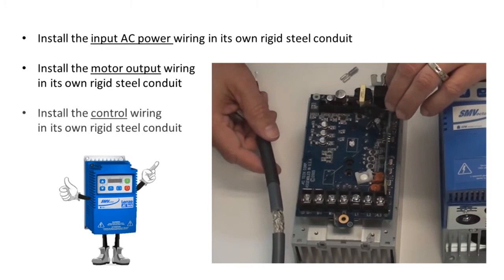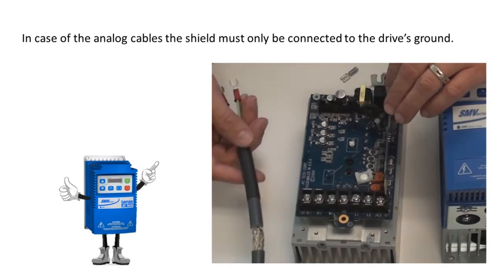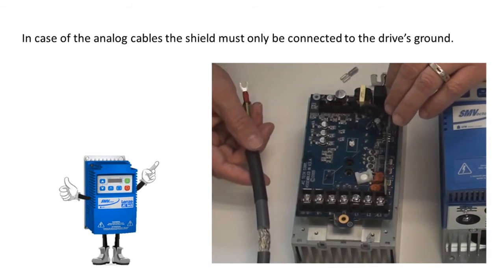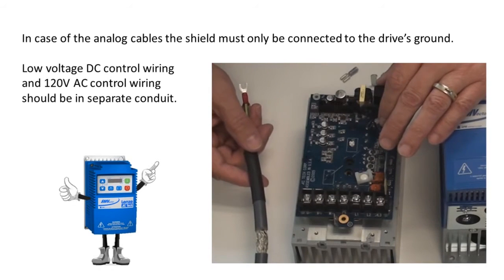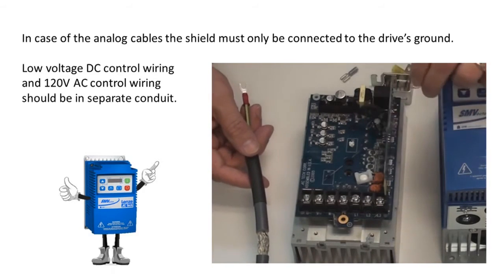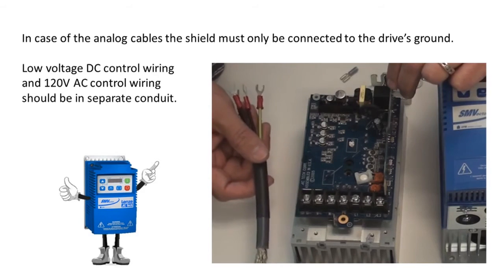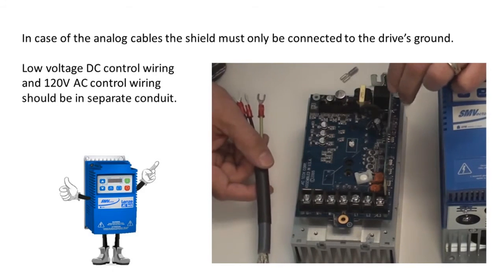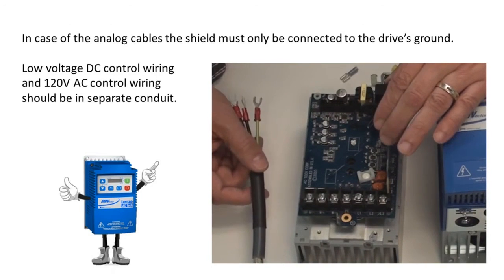Step three is to install the control wiring also in its own rigid steel conduit. In case of an analog cable, the shield must only be connected to the drive's ground. Low voltage DC control wiring and 120 volt AC control wiring should ideally be in separate conduit, but we know with many panel designs, this is not always possible.